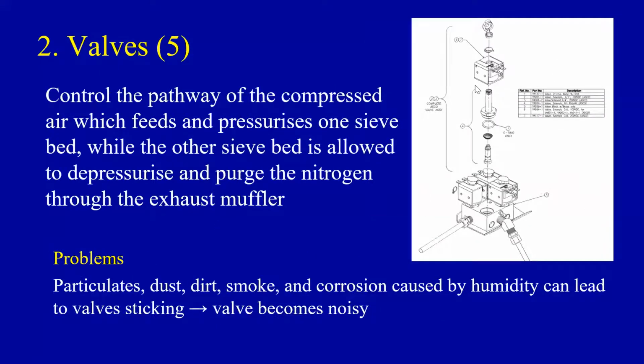The second part is the valves. And the valves, as I said, they control the flow of gas that comes in, is pumped by the compressor, and it goes from one of the sieve beds to the other sieve bed. So it goes at one for say 5 seconds, and then moves to the other one. And that movement of gas is controlled by the valves. And the only reason to explain about the valves inside an oxygen concentrator is sometimes the valves get a bit sticky, or they get a bit dirty.